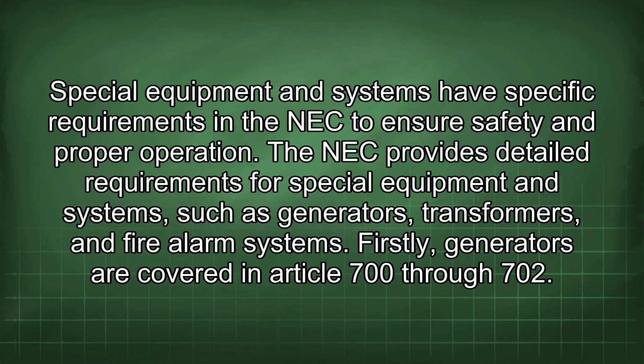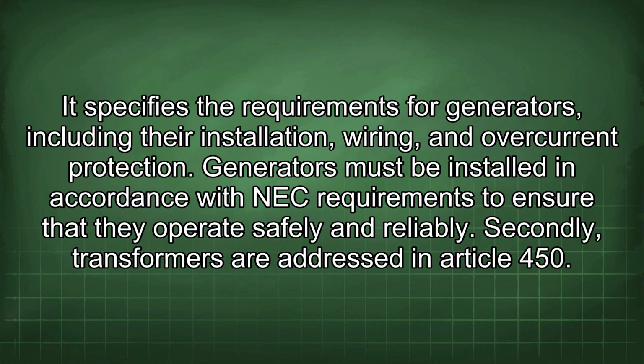Firstly, generators are covered in Article 700 through 702. It specifies the requirements for generators, including their installation, wiring, and overcurrent protection. Generators must be installed in accordance with NEC requirements to ensure that they operate safely and reliably.